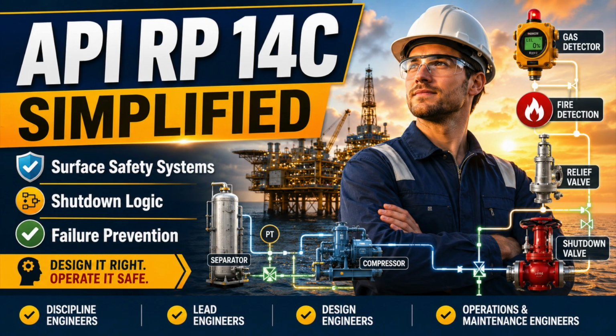Protective shut-in should normally stop hazardous energy at its primary source. When a downstream vessel develops high pressure, closing only its inlet can create pressure escalation upstream. The header rises in pressure, then the flow line rises, then the well finally shuts. You have forced multiple components into abnormal conditions and depended on several extra safeguards. Where practical, shut the well, stop the pump, isolate the compressor, remove the fuel, or divert the heat source directly.